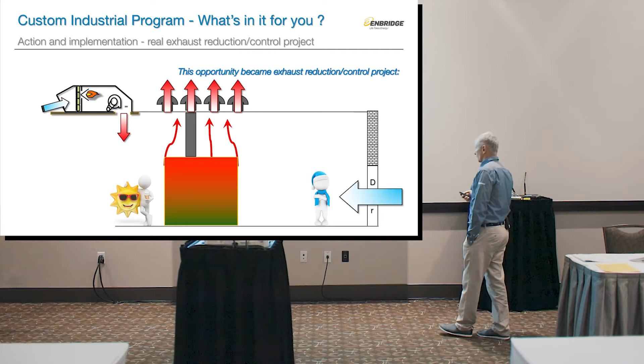Other one, you remember this one where one is freezing, one is nice and toasty? That became the exhaust reduction system. That's actually the facility where I showed you that business case that had multiple operating parameters. What really happens, every time you have this imbalance, is people put a process that requires makeup air into the facility. And then, by design, because everybody who does this kind of job and engineers have to put the same amount of makeup air, minimum, to balance the two. But then this process starts emanating heat, which gets more pronounced in the summertime. So they complain, it's too hot, I can't work here.